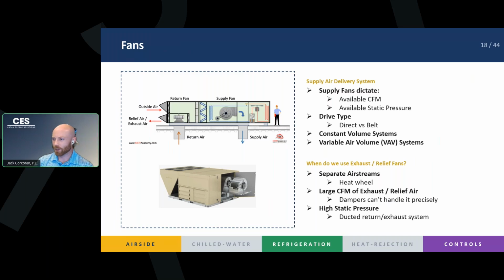You can have a couple different types: direct drive and belt drive. The way you control the fan on the supply side can be constant volume, or it can be variable air volume, depending on how you want to control the temperature in the space. We'll talk about that a little bit later on. But that's your supply side, right? All your supply air needs to be pushed out through the air side loop somehow, and that's dictated by your supply fan. You can also have exhaust or relief fans.